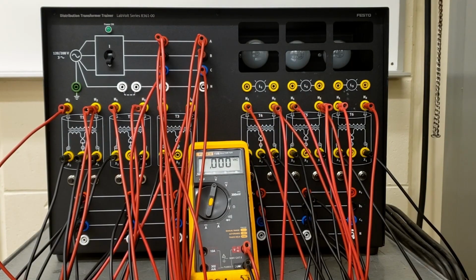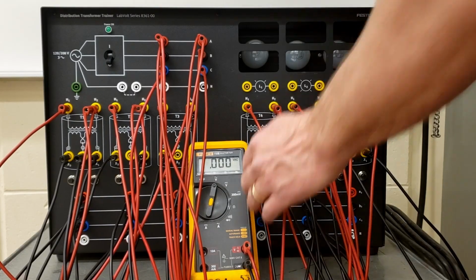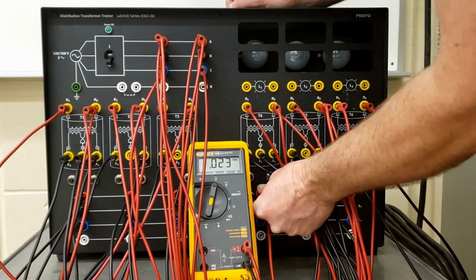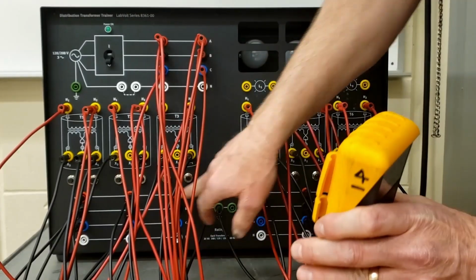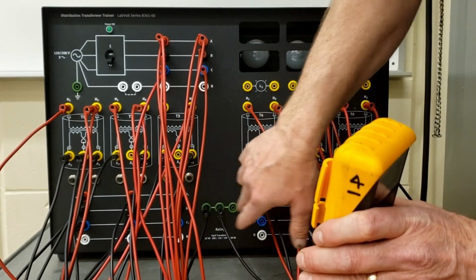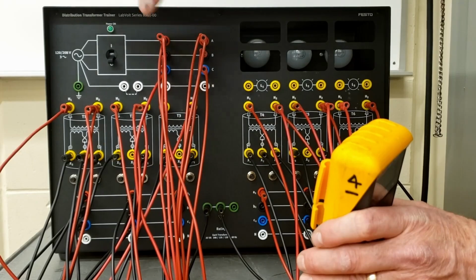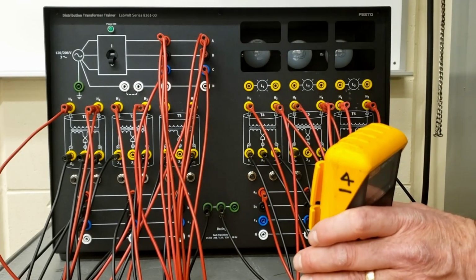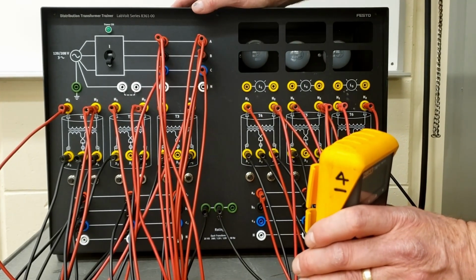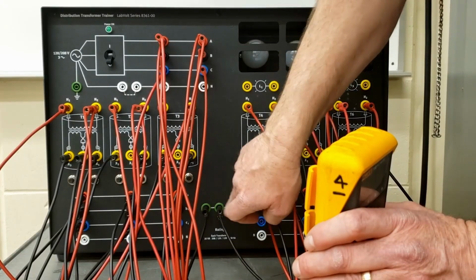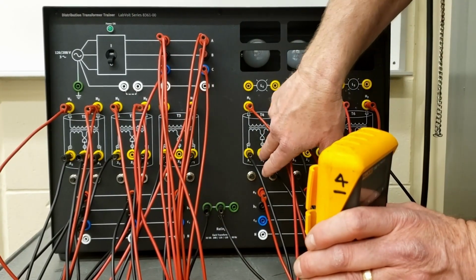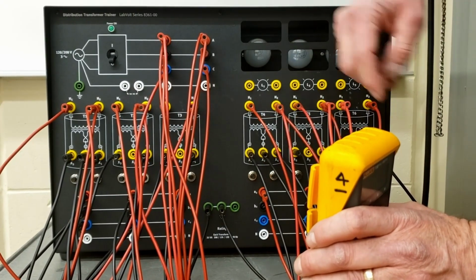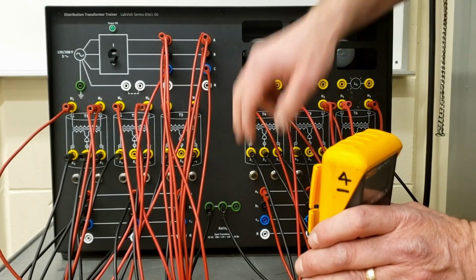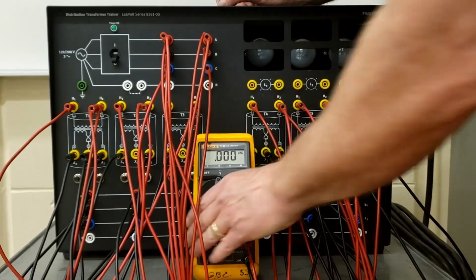Once we turn this on, they want us to look at the voltage between the two buses, so I'll check the two A buses, looking at the potential difference between them. Since everything's hooked up in parallel with the same phasing, we should have 0 volts between those. Notice that X2 of both transformer 4 and transformer 1 have been grounded there.